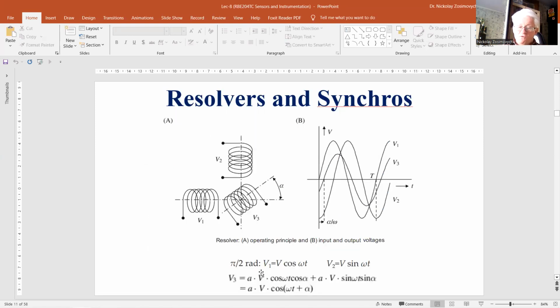Inductive sensors for the full range of 2 pi are the resolver and the synchro. These types are based on a variable transformer as well, with fixed and rotating coils. The coupling between primary and secondary coils depends on the angle between the coils. The resolver, as you can see in figure A, essentially consists of 2 fixed coils, usually named the stator, making an angle of half pi, and 1 rotating coil, the rotor.